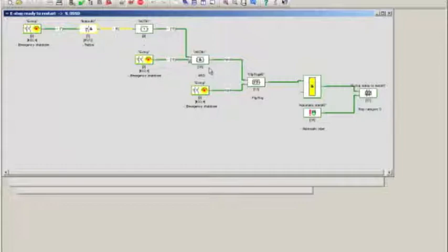Generally speaking, if you use the NOT function in something that is diagnostics related, like this particular set of logic, this does not control any output, this does not control a motor, it is simply utilized to give me a diagnostics output, a signaling output to the PLC, then of course there is no harm. But if you use it in any logic that has anything to do with a safe output, you need to be extremely careful, and the best advice is probably to not use the NOT function at all.